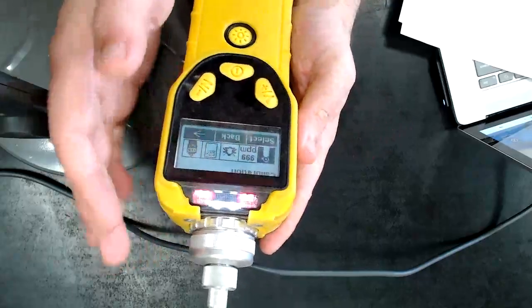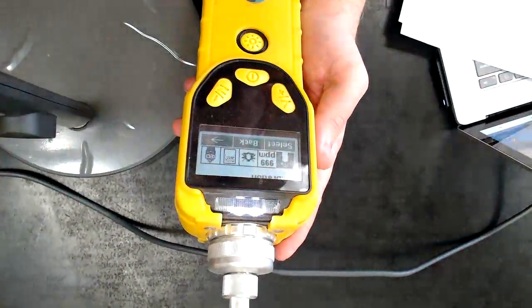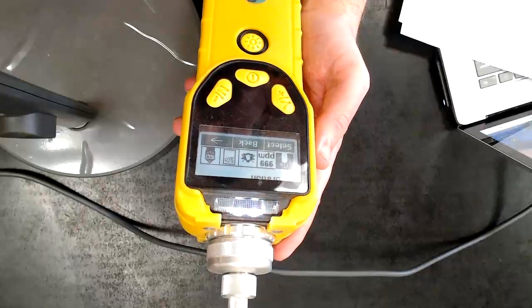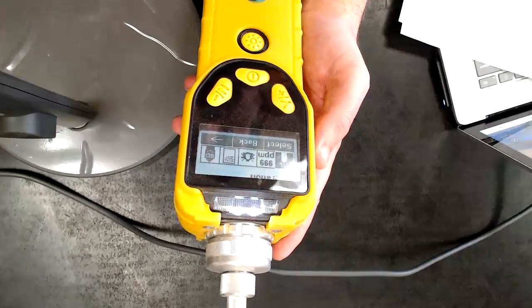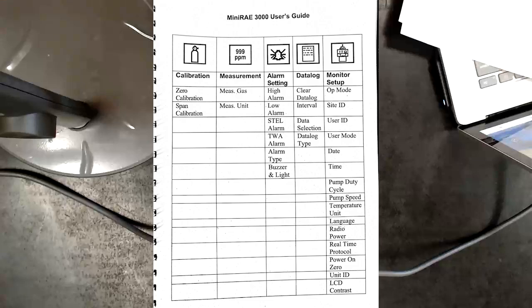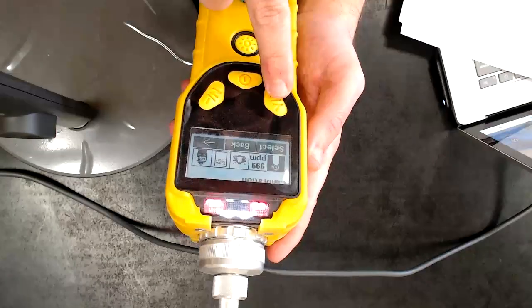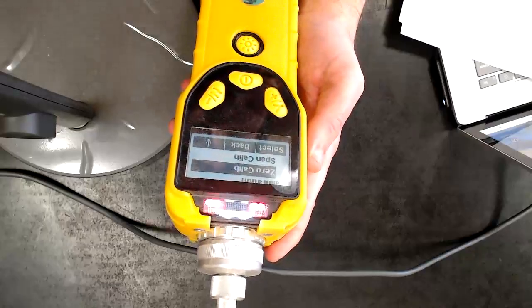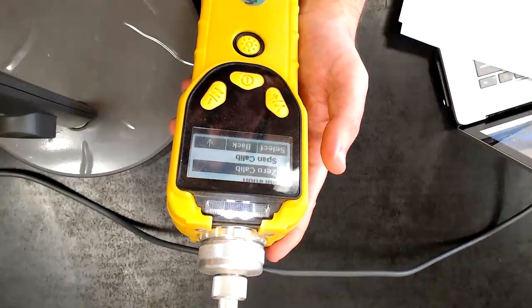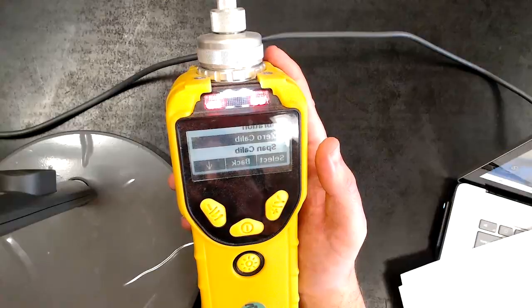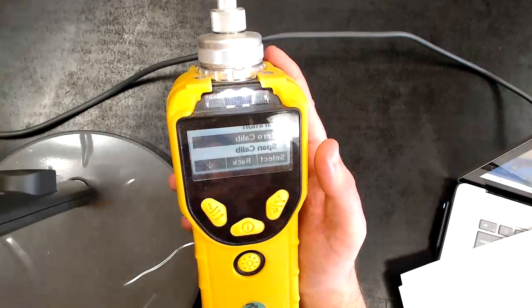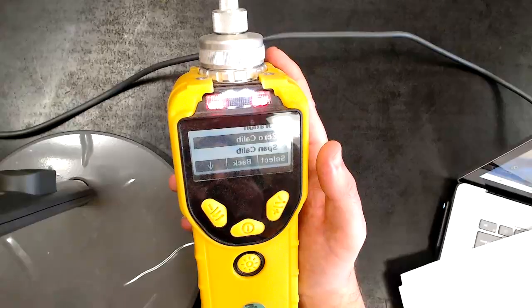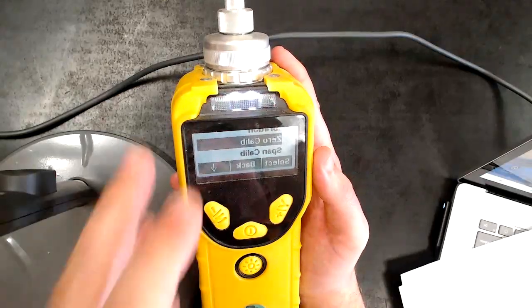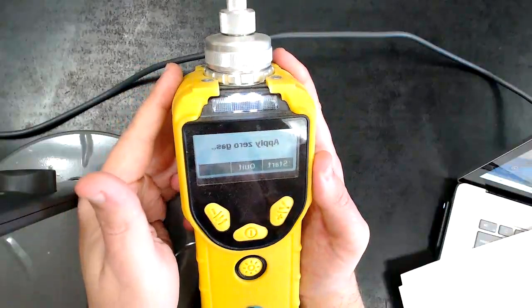We already entered the password for this one. We kept it at the default of 0000, so four zeros. This first button is to change the calibration. When we select it, it gives us two options to calibrate: a zero calibration and a span. For the zero calibration, we make sure we're not around anything, just ambient air. We're in the lab, nothing's around us, so we'll select that to zero calibrate.